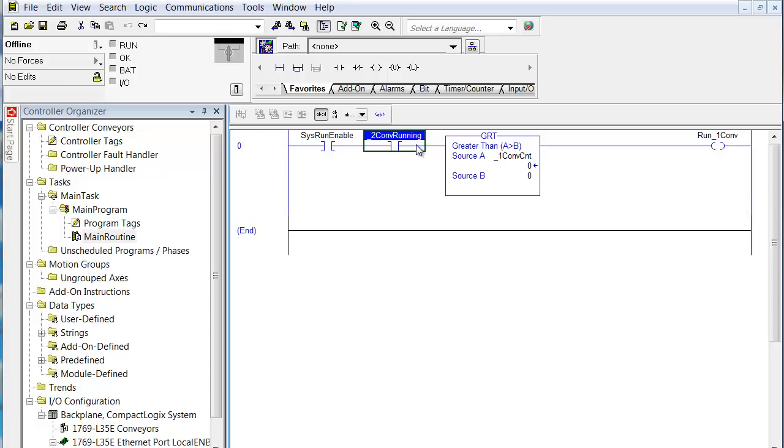So anyway, two conveyor running is not something you control. It's a condition that you are acquiring from another controller from a downstream process. So if two conveyor is running, you could rename that, we want product, we want cartons. Whatever it is you're supplying, the downstream part of this system, it wants it. So you could call that product request. However, the way that it requests the product, it turns on the conveyor, gave you access to the aux contact, so you know that it wants product.